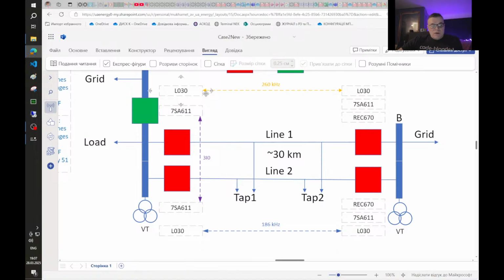In L030 the main function is phase-differential protection, and it has high-frequency communication channels. In this particular case, the communication channel on the first line was damaged, and only on the second line was a communication channel in work. I wrote here frequencies. So on the first line it is 260 kilohertz, and on the second line 186 kilohertz.